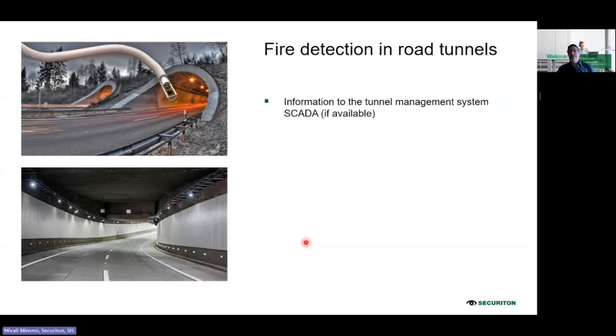Then fire detection in road tunnels is important, so that all the information goes to the SCADA system if it's available, because here we really get the temperature profile, and therefore the system must have this possibility to be integrated. First, because as I always repeat, the most important thing is that as soon as we trigger an alarm, we need to close the tunnels.